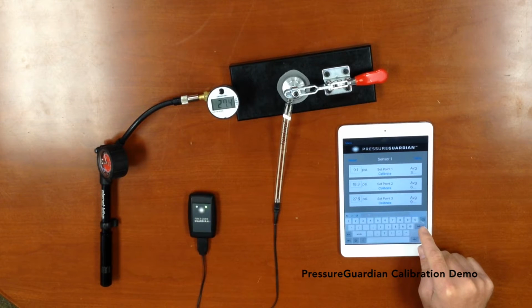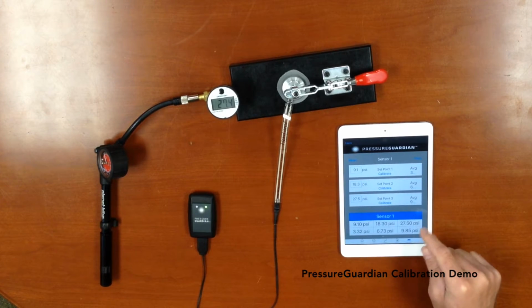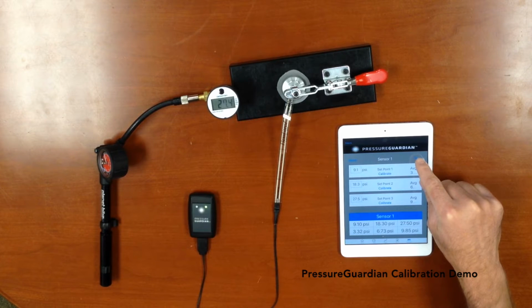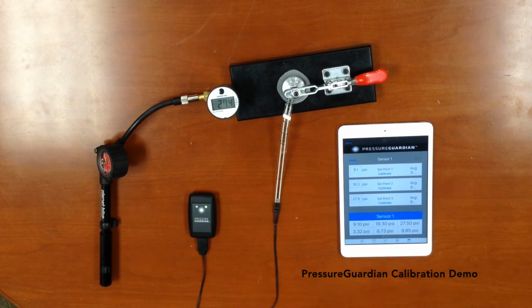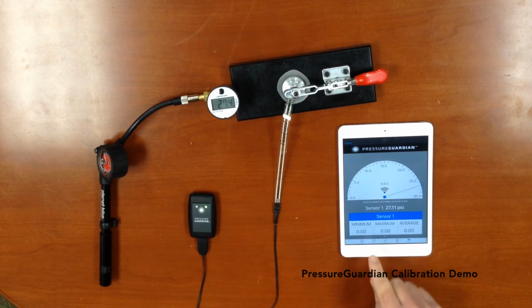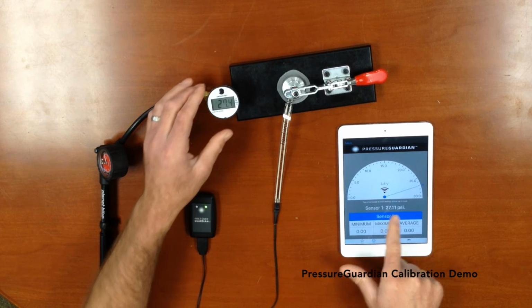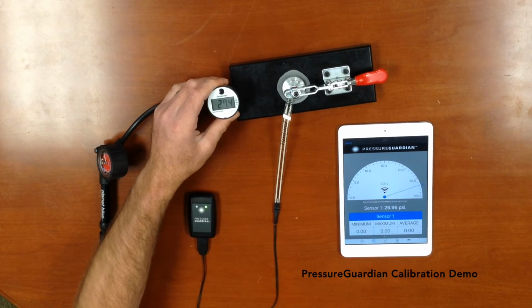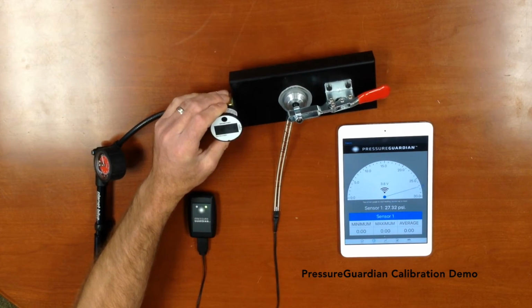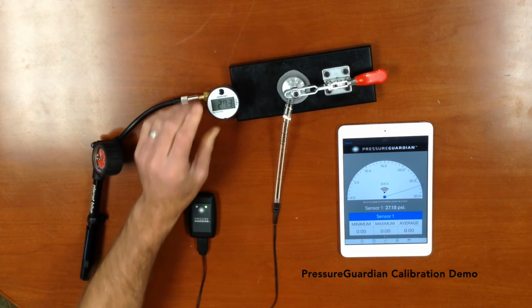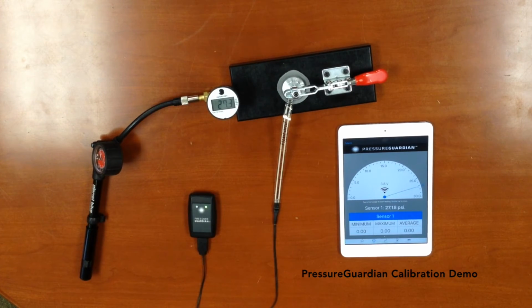Now we're going to hit return to drop that screen down, and I want to hit save. It's important that you hit the return button before you hit save to ensure that all the numbers have properly saved. Now I'm going to go back into my stats page, and you can see now that our PSI pressure is around 27, and our PSI pressure on our gauge is 27.